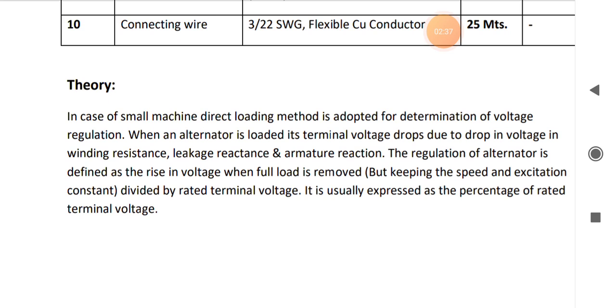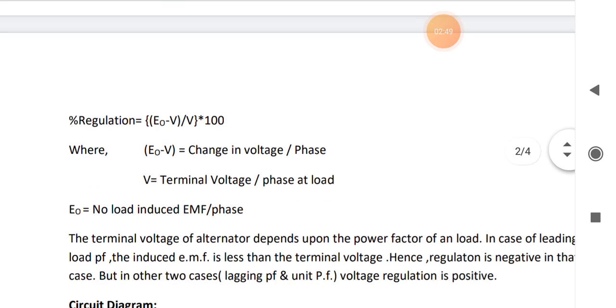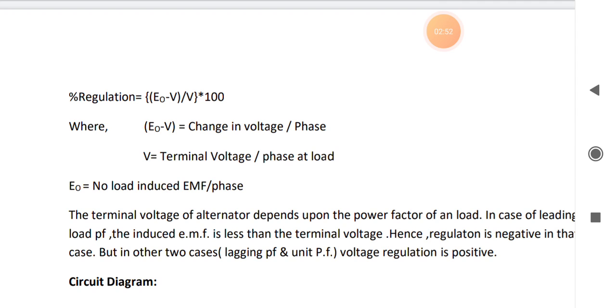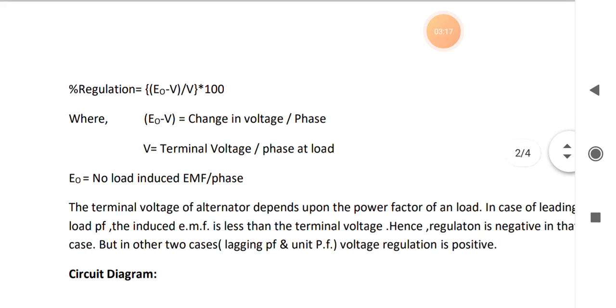It is usually expressed as the percentage of rated terminal voltage. Percentage regulation is given by the formula (E0 minus V) divided by V into 100, where E0 minus V is not vectorial difference, it is the arithmetic difference. Capital V is the terminal voltage. E0 is equal to no load induced EMF per phase.